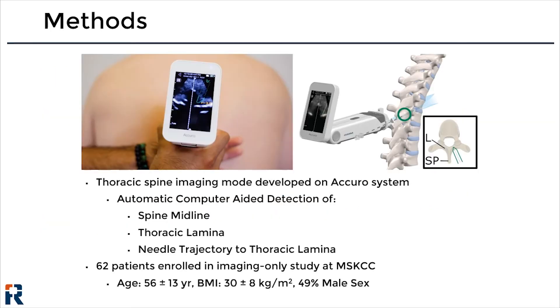We developed a thoracic spine imaging mode on the Accuro ultrasound system that automatically detected the spine midline and the thoracic lamina, and provided a prospective needle trajectory for needle guidance to the thoracic lamina, assuming a paramedian needle approach. We enrolled 62 patients undergoing abdominal or thoracic surgery at the Memorial Sloan Kettering Cancer Center and collected ultrasound images of their thoracic spine to evaluate the accuracy and performance of the algorithm.